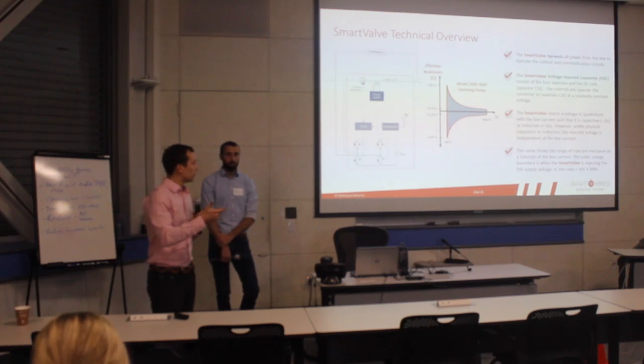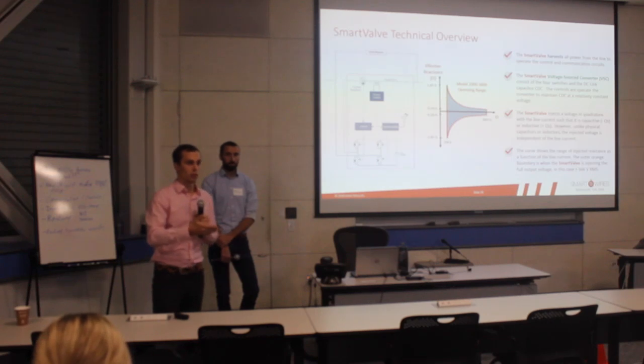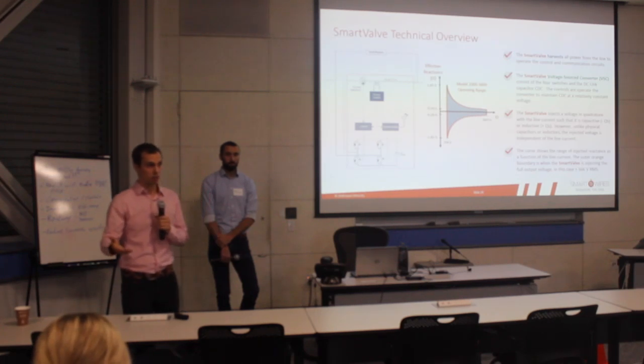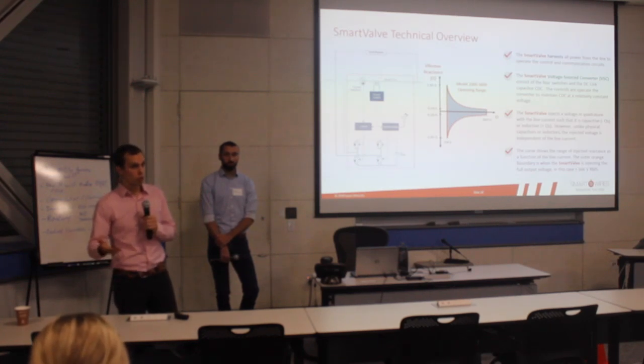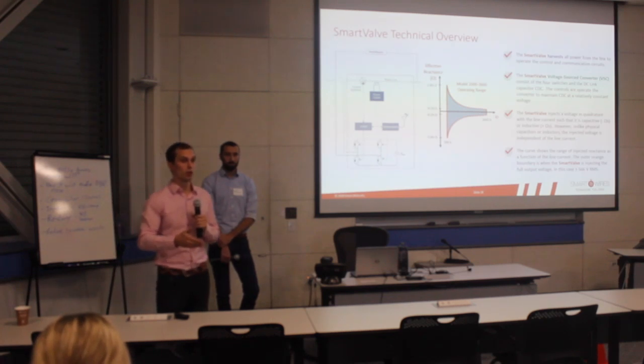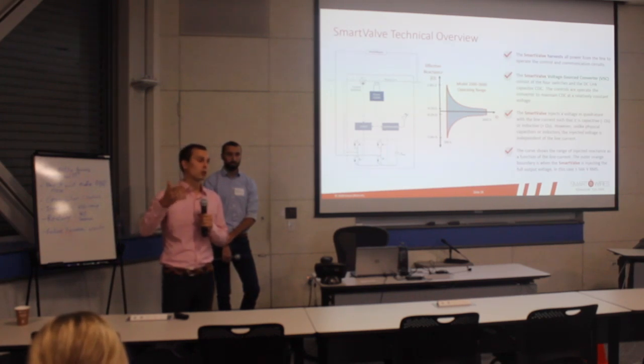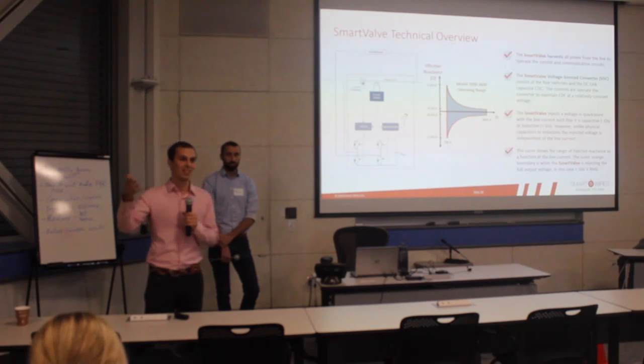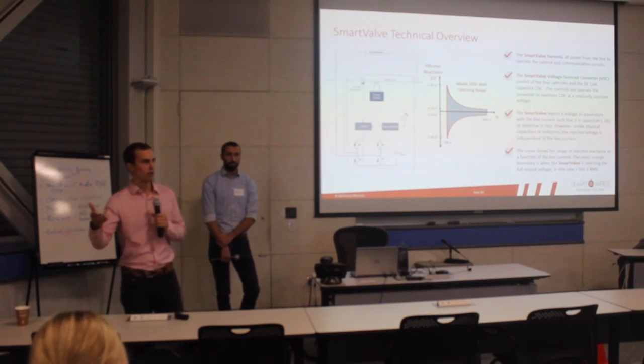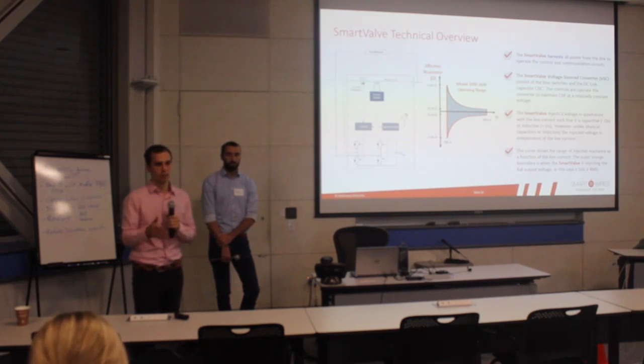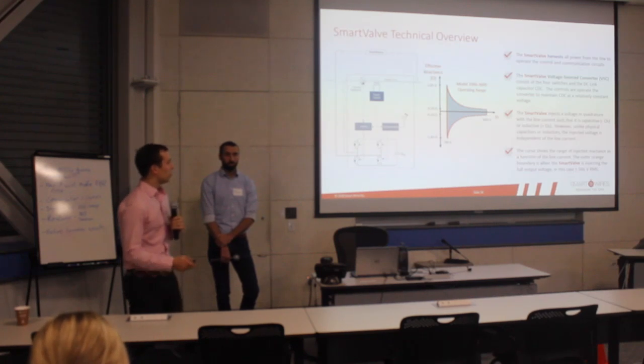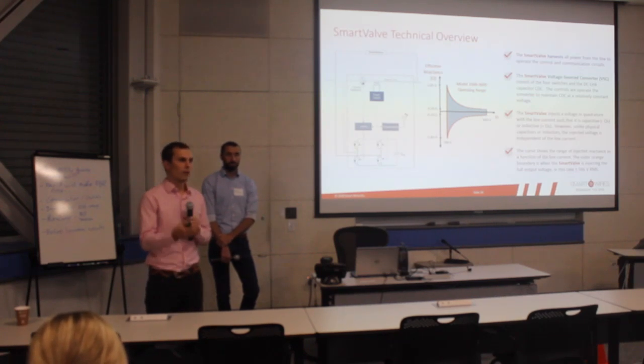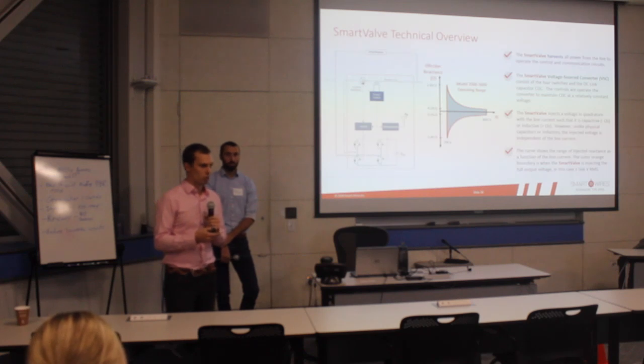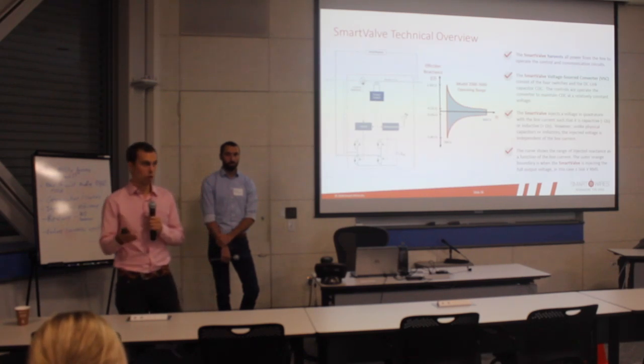But what is very difficult to handle on a transmission line is what happens when a fault comes. When a fault comes, you go from those 2,000 to 4,000 amps to where our product is rated for: 170,000 amp peak, about 60,000 amps RMS. That device, the smart valve I showed, is what's doing the power flow control, acting like an inductor or capacitor.